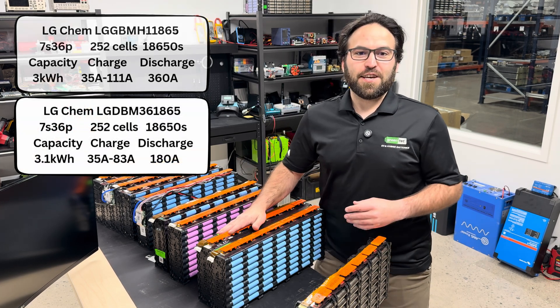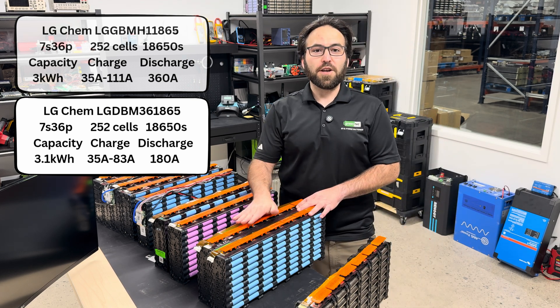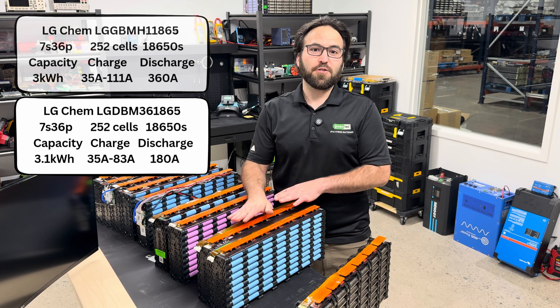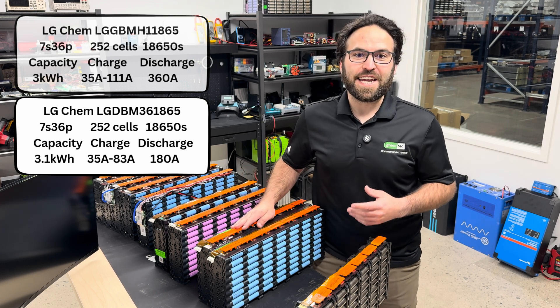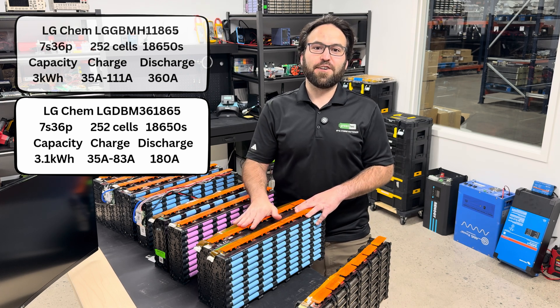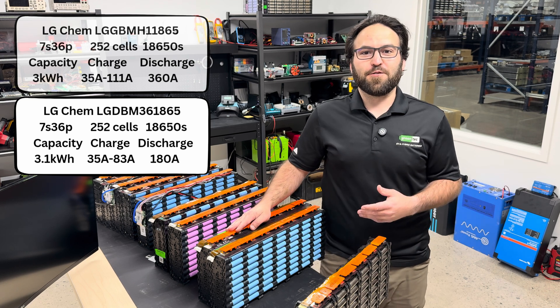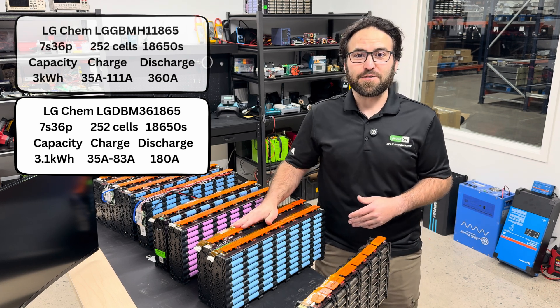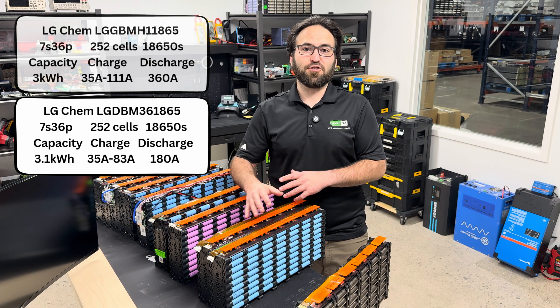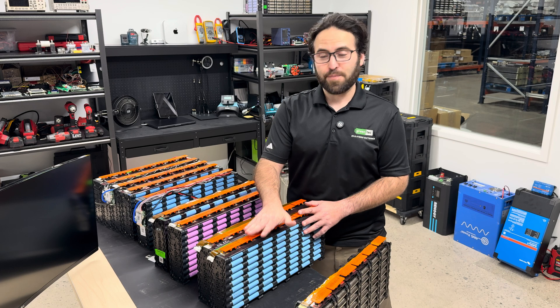The second LG Chem is the LGDBM model. This holds 3.1 kilowatt hours, so it's slightly larger capacity, but it has a lower discharge rating of 180 amps peak. The charge rating under 75 degrees Fahrenheit down to 0 is 35 amps, while over 75 degrees Fahrenheit is 83 amps. So this one has a little bit less charge and discharge, but a slightly higher capacity rating.